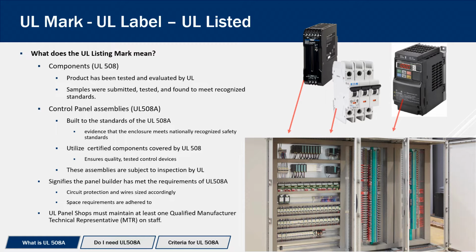This also signifies that the panel builder has met the requirements of UL508A, which could be like circuit protection, wire sizing, space requirements are adhered to, all of that. And each one of these shops needs to have a qualified manufacturer technical representative on staff.